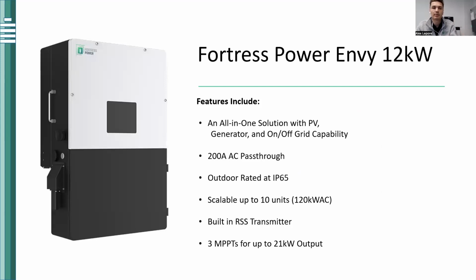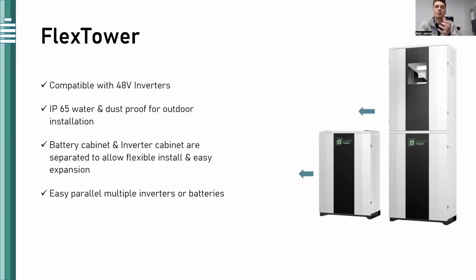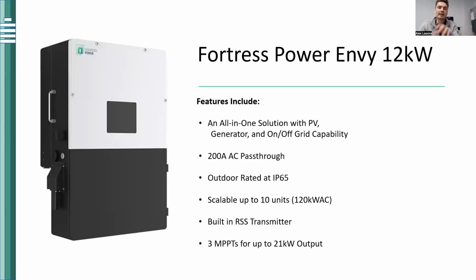Here's the inverter I talked about - it is one box, a 12 kilowatt inverter with 200 amps of AC pass-through. It's outdoor rated, has 3 MPPTs for up to 21 kW of PV, and can send up to 18 kilowatts to the AC output. It's all in one - you have a generator input, PV, on-grid and off-grid capability. You can also do 3-phase 208 volt projects for developers and installers, or if you're a homeowner on a 208 volt service, you have a very nice home, I'm sure. It is outdoor rated as well, so that's where I really talk about how we have an outdoor rated battery, an outdoor rated inverter, and an outdoor rated cabinet.